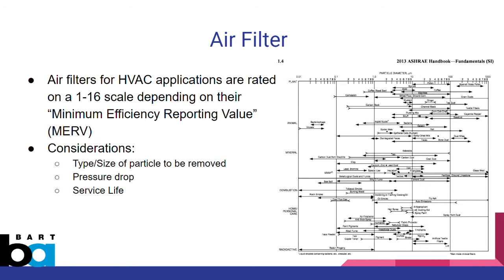The ASHRAE handbook covered all aspects of required HVAC considerations, including the implementation of an efficient air filter. The air filter is an essential component that ensures the health of BART riders by making sure that the air they breathe is clean of any pollutants and debris from outside conditions. Air filters are rated at different grades to meet different application specifications. Ratings are based on the minimum efficiency reporting value, or MERV, and are normally from a scale of 1 to 16, with higher grades usually for hospital applications at 17 to 20 MERV.